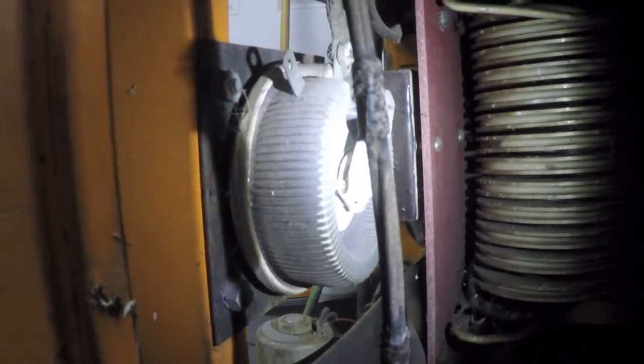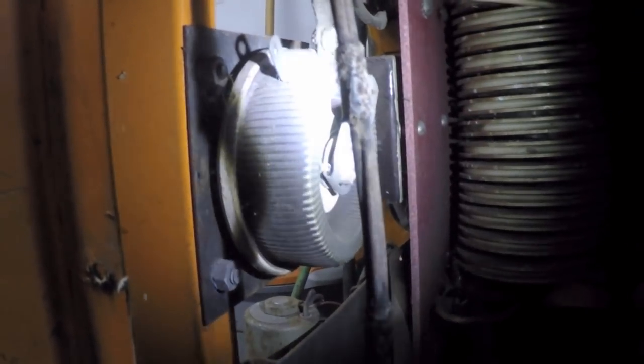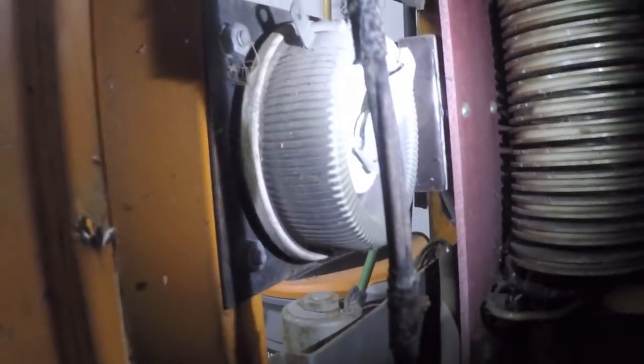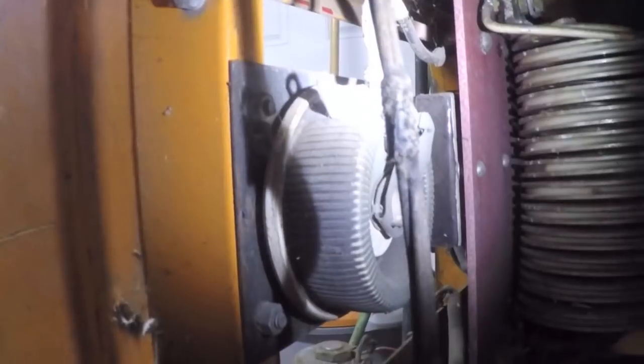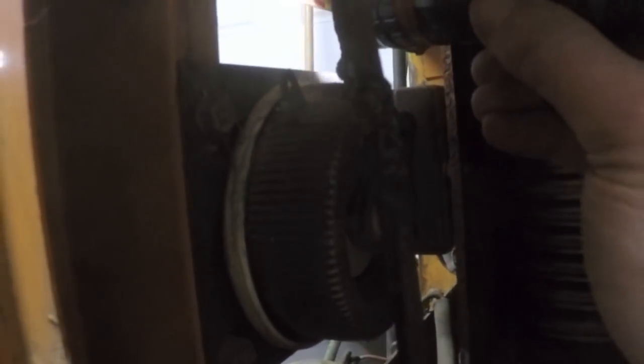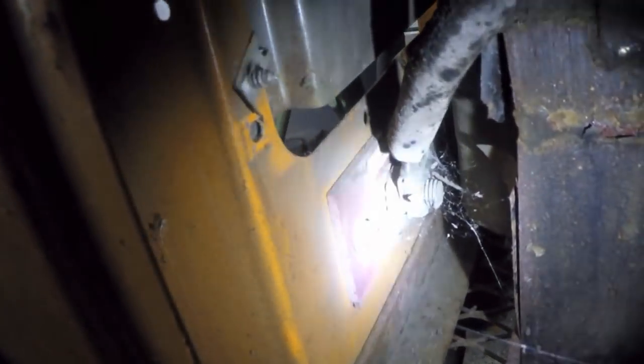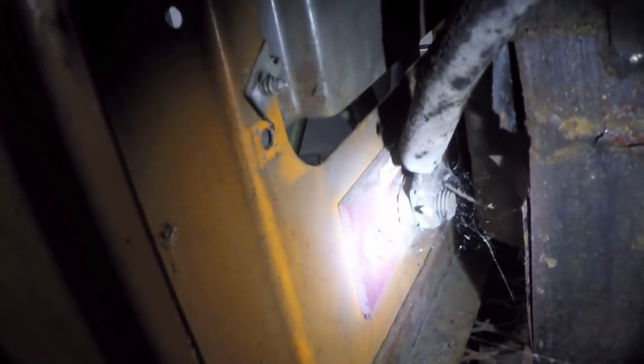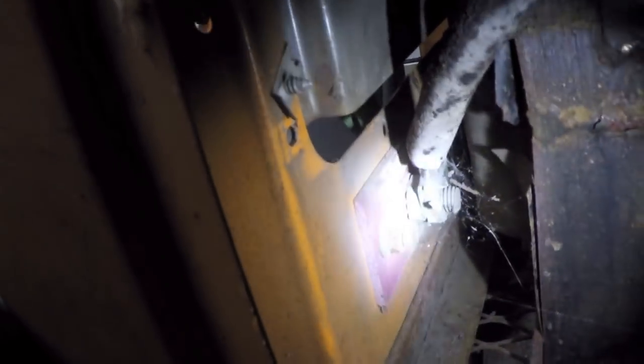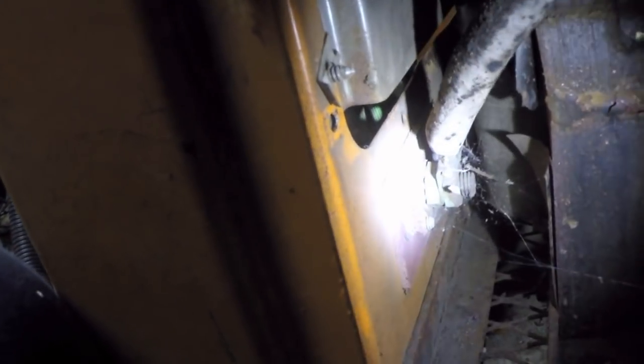That's the rheostat, which acts as the intensity control for the high frequency. Those connections have a little corrosion on them, but they seem tight. There's even some cobwebs and stuff down over here, and that connection has a little corrosion on it too.